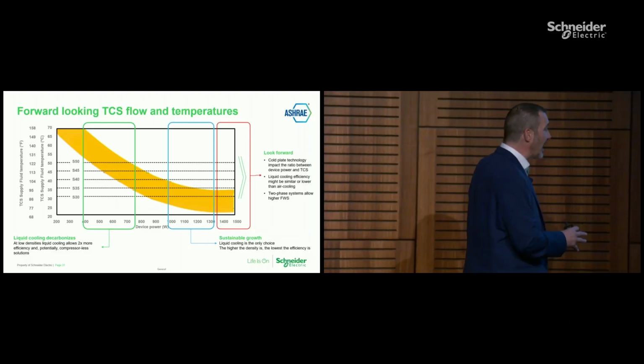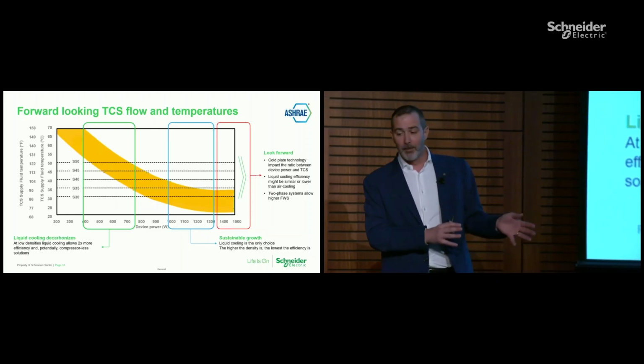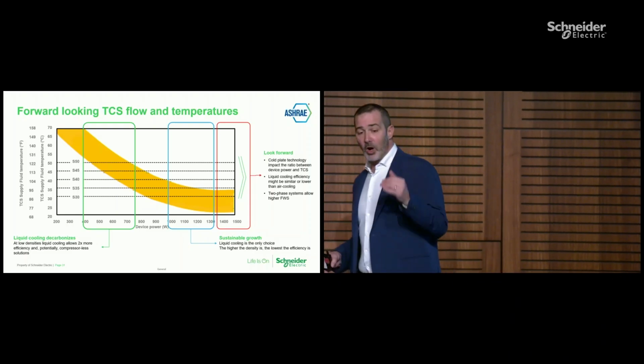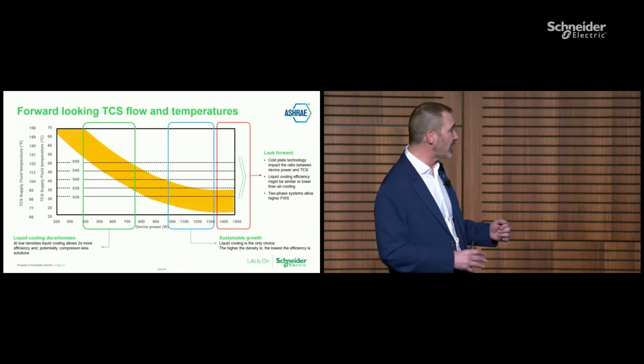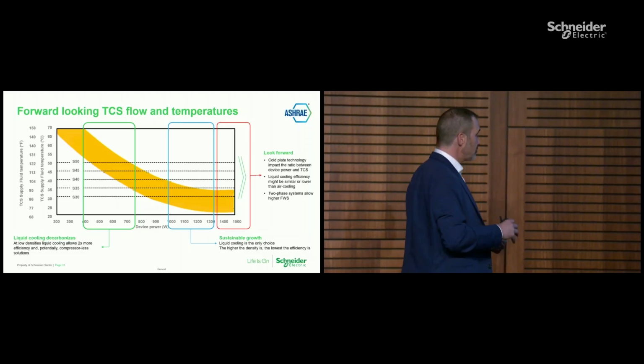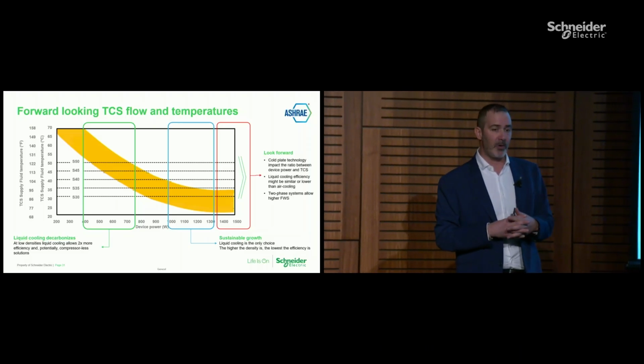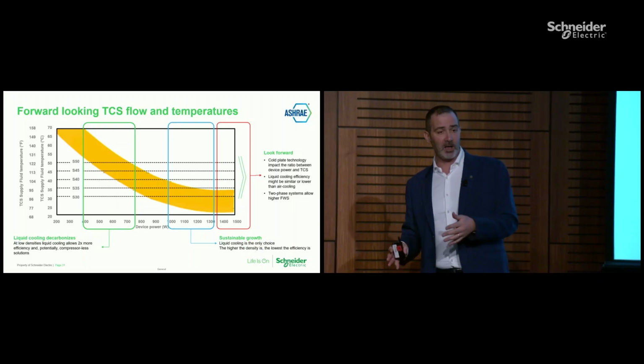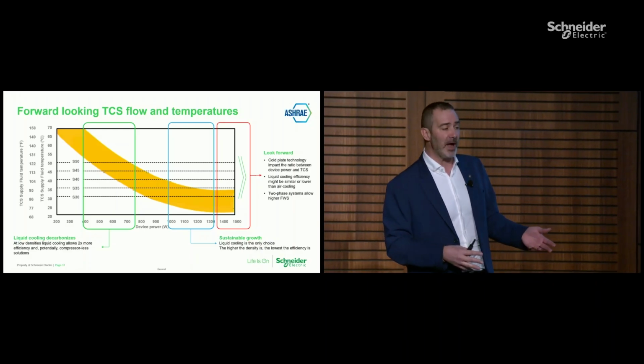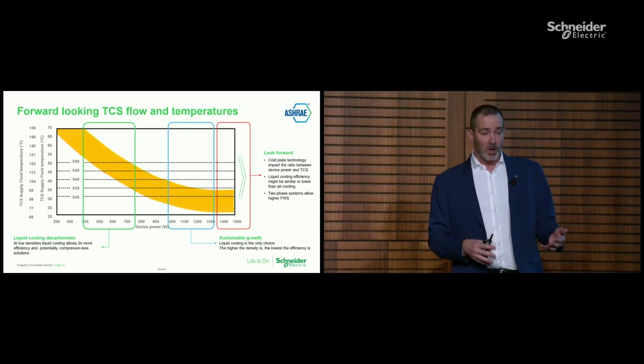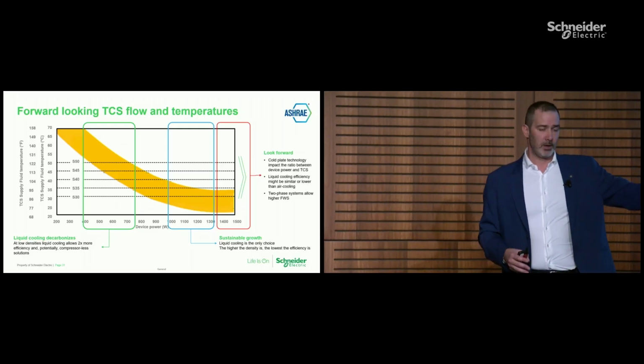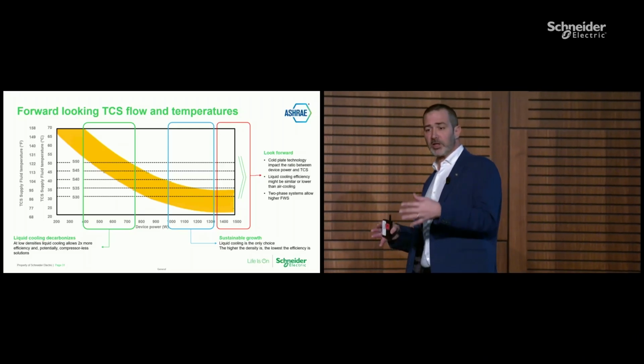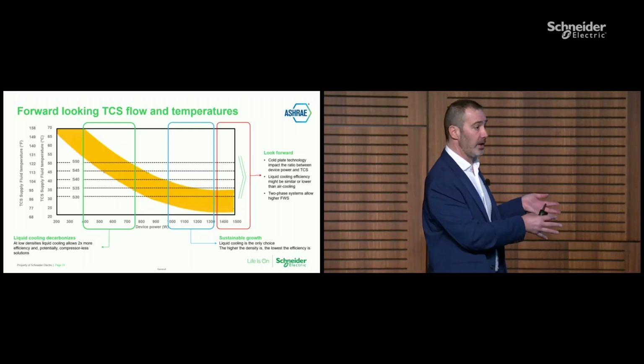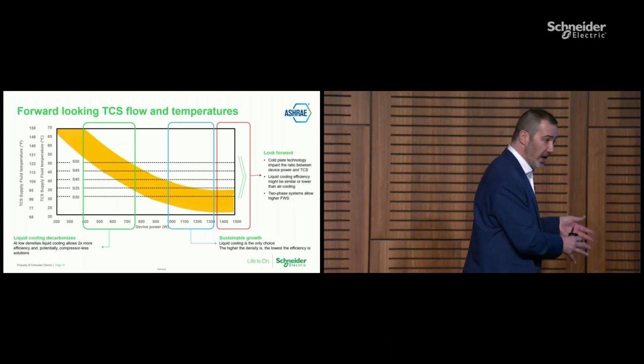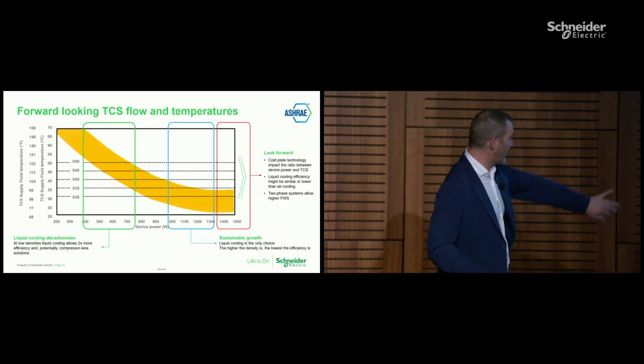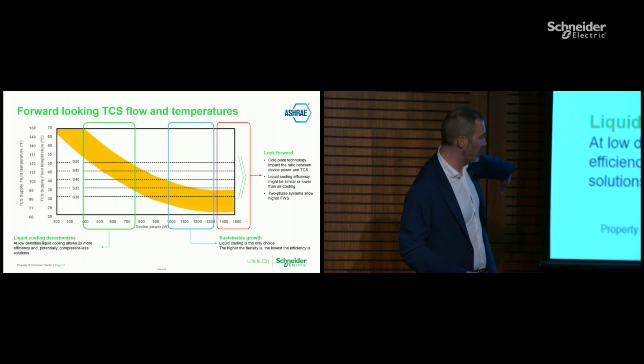But the problem is that the density is going to move, and the more density you have, the lower the temperature will be. You see that at more or less 50-60 kilowatts per rack, you may be at 30 or 25 degrees C. So in the long run, you might have water temperature even colder than what you have today with air.